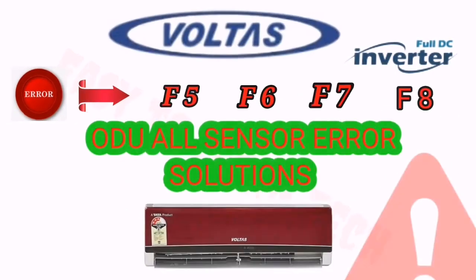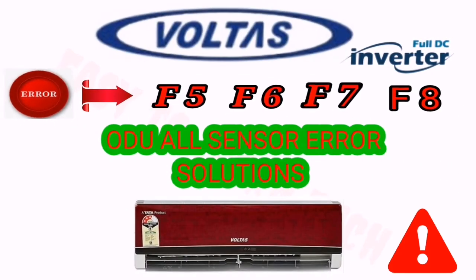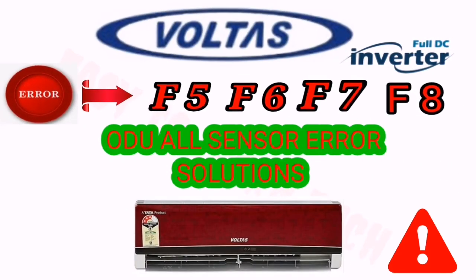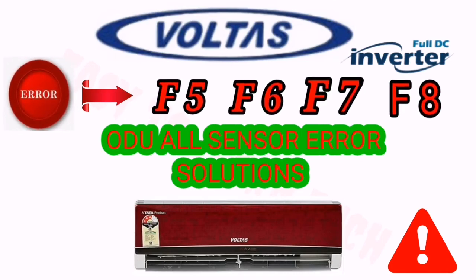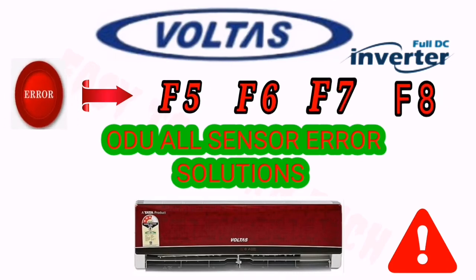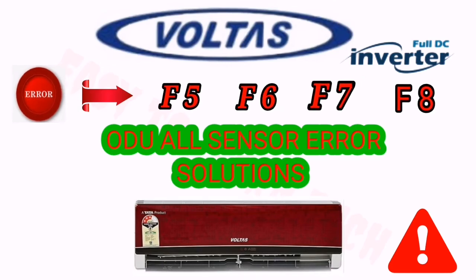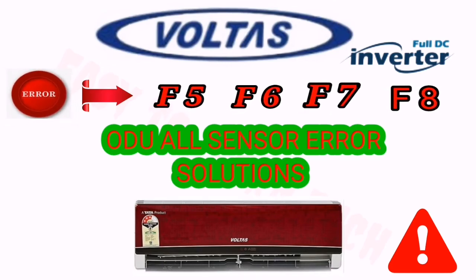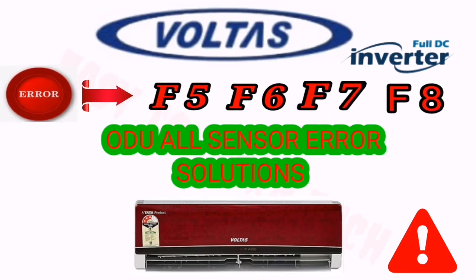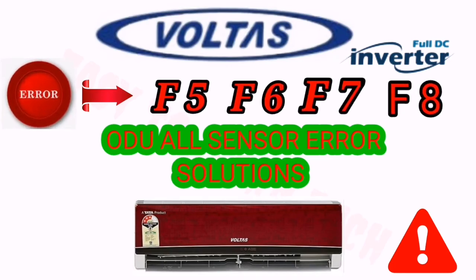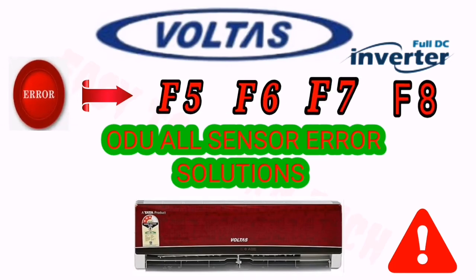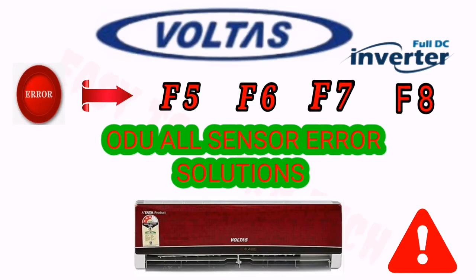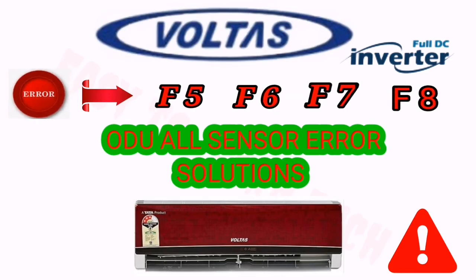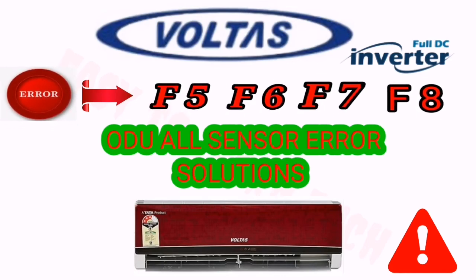Let's see the next error code. When you see F5, F6, F7 or F8 on your outdoor unit, these four are for the outdoor sensor error. F5 stands for the discharge sensor, F6 is for the outdoor suction temperature sensor, F7 is for the coil sensor, and F8 is for the outdoor ambient temperature sensor. And for all these four sensors, we have the same troubleshooting process.